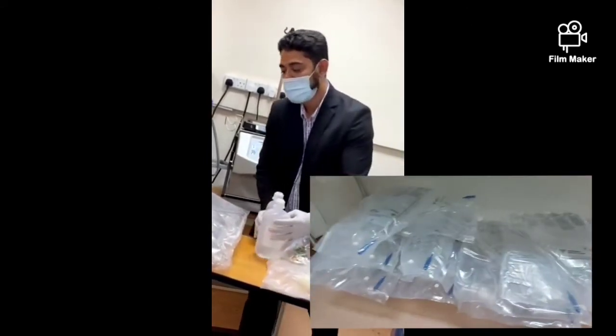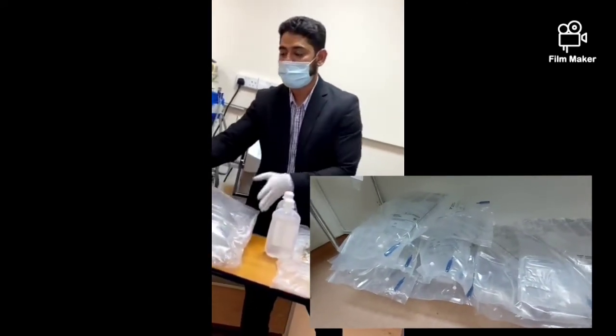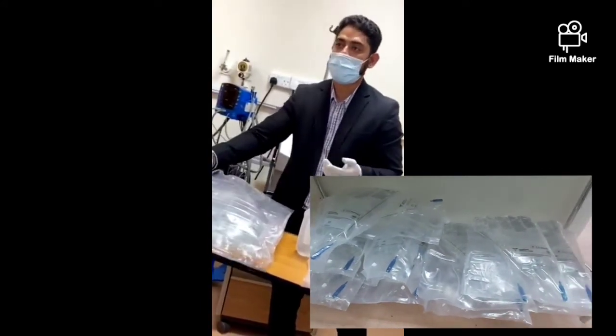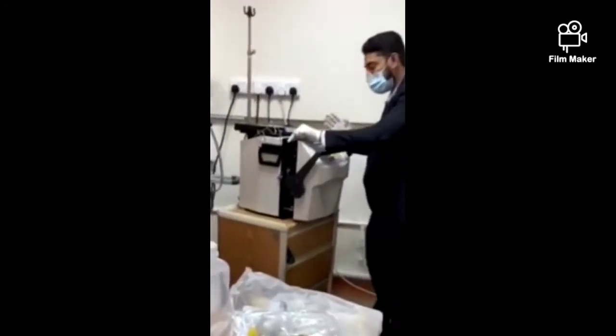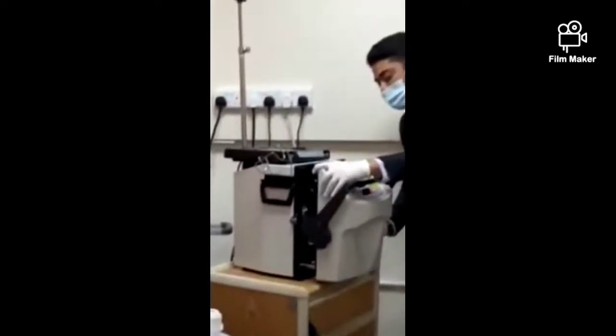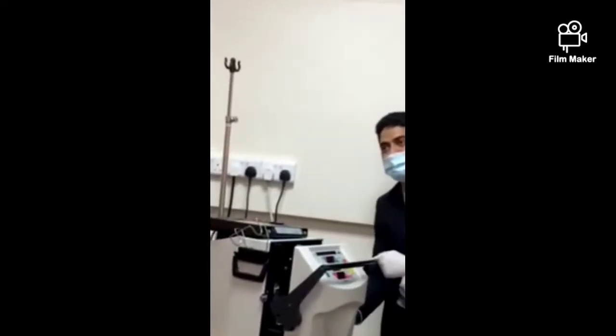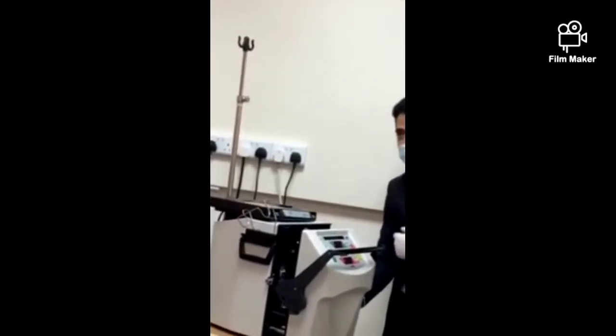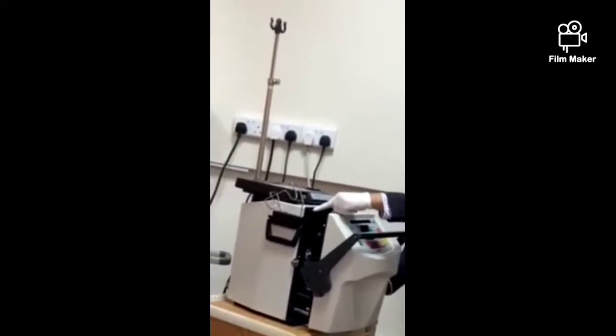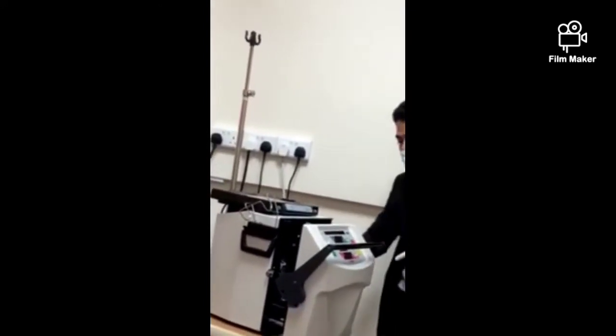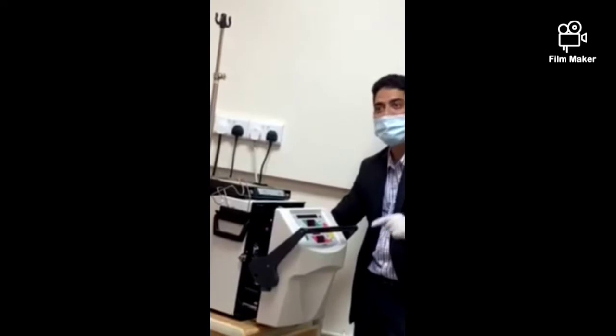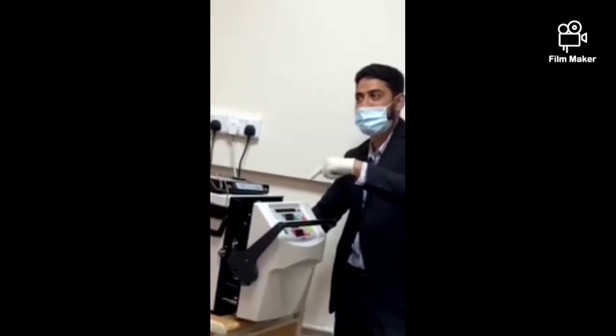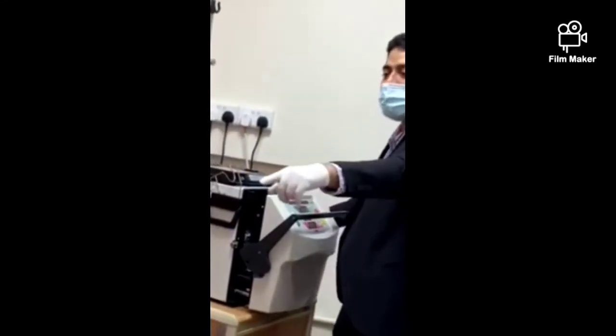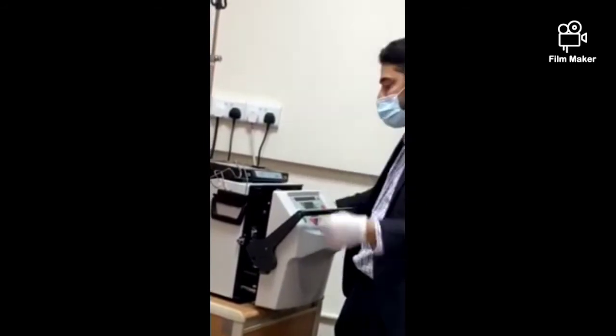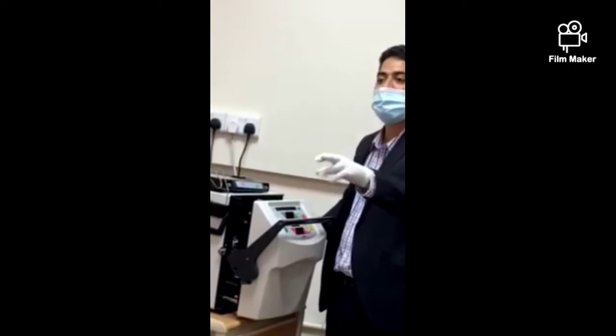Okay. And next, we need the dialysate. This is our dialysate as K2, K1. This is the venous. Okay. And at the bottom, at the right side, this is the arterial air detector, and the left side is venous. And in the center there is also a square. That is the dialysate air detector. If for example the dialysate finishes and air comes, it will detect. The machine will not stop, but it will only tell you that it finished.